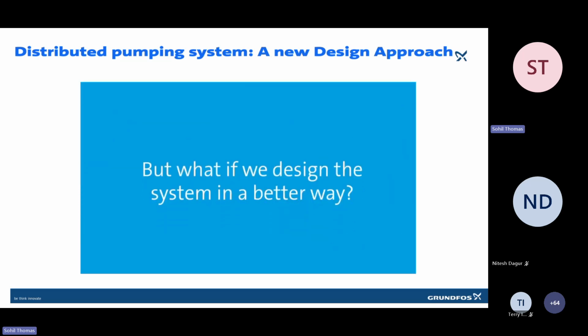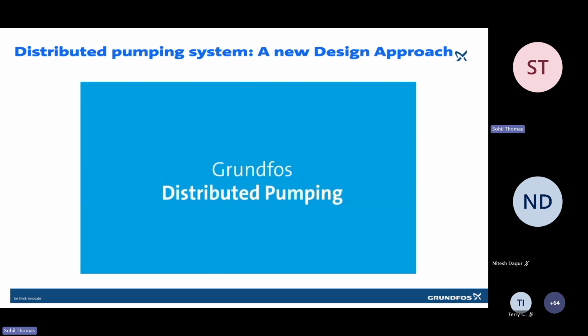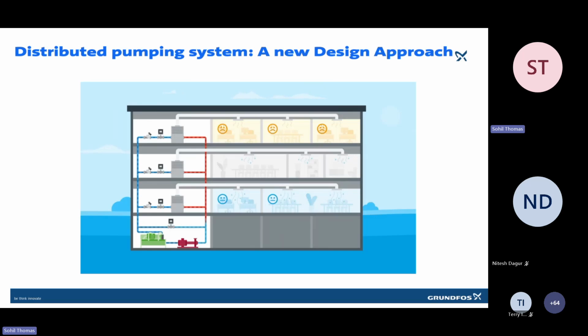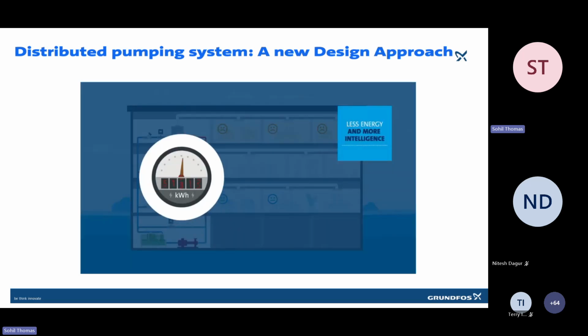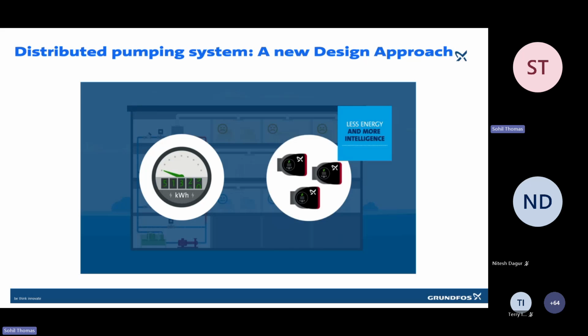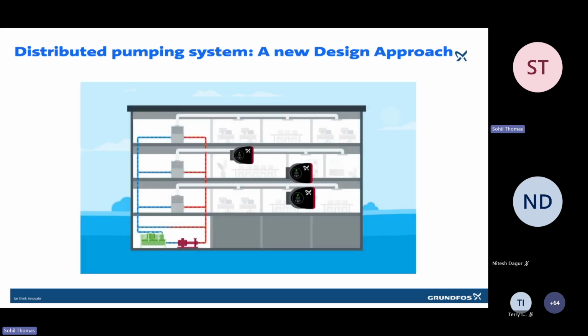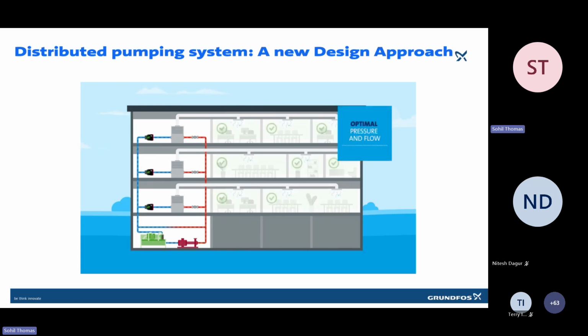But what if we design the system in a better way? Our solution is Grundfos distributed pumping. By replacing valves with intelligent pumps, we use less energy while bringing more intelligence to your cooling system. A Grundfos distributed pumping system uses the maintenance-free Magna 3 circulator and low-pressure non-return valves to prevent backflow. The distributed pumps ensure optimum pressure and flow at each terminal unit at all times.